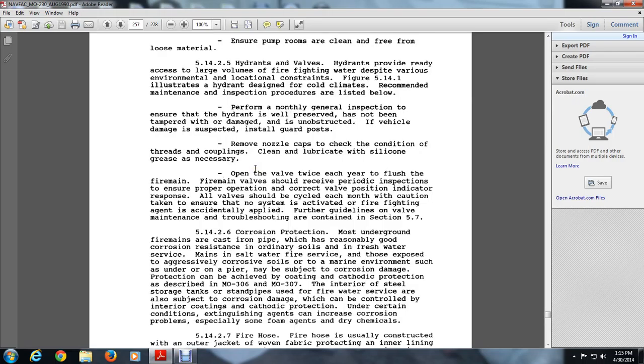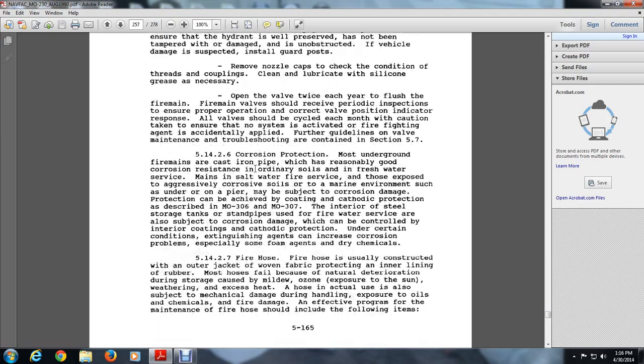Interior steel and storage tank standpipes used in fire water services are also subject to corrosion damage, which can be controlled by interior coatings and cathodic protection. Certain conditions and extinguishing agents can increase corrosion problems, especially foaming agents and chemicals.